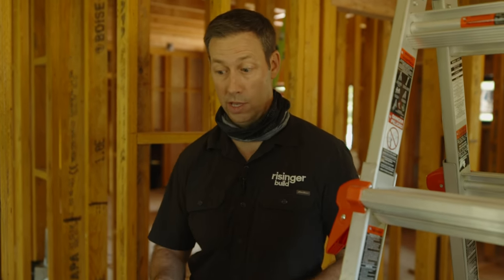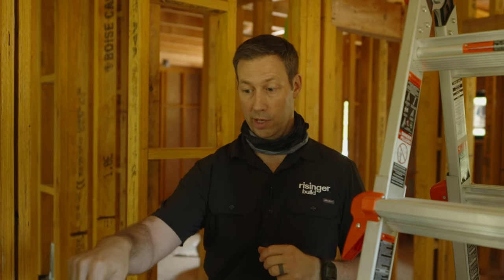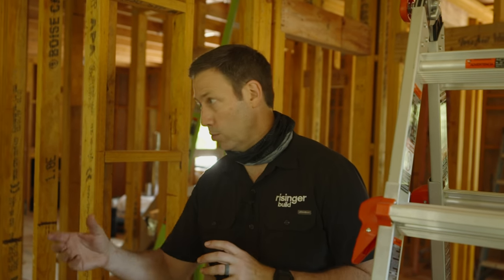When we commission this, we'll put a flow hood up against the ceiling and check how many CFM we have coming out - do we need more or less - and dial it in right here. So everything gets done later, there's no weirdness with needing a 2-inch or 3-inch or 6-inch duct here. No, everything goes with those vacuum cleaner looking hoses - comfo tubes - and later we can dial it in.